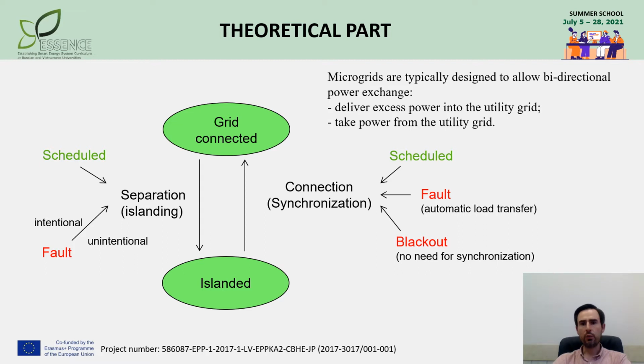The grid-connected operation may also be established due to the scheduled equipment maintenance of a normally islanded microgrid for some period of time, like minutes, hours, or even days, when remaining distributed energy resources are not able to cover microgrid demand. If a transfer from islanded mode to grid-connected is required, synchronization conditions shall be established. Connection to the main grid is also required in case of internal microgrid faults.